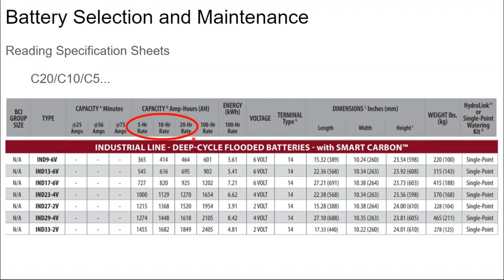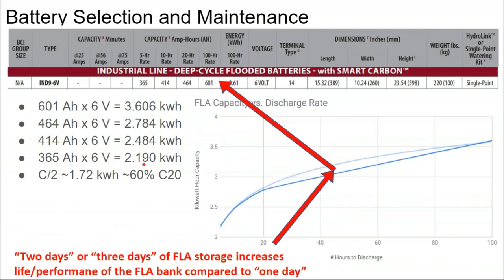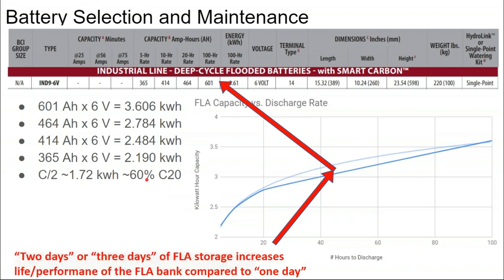What that means is if it's discharged fast, over 5 hours, the total output will be 365 versus 464. When you look at discharging over a 2 hour time frame versus a 20 hour time frame, you're only going to get 60% of the energy that could come out of it if it was discharged more slowly.